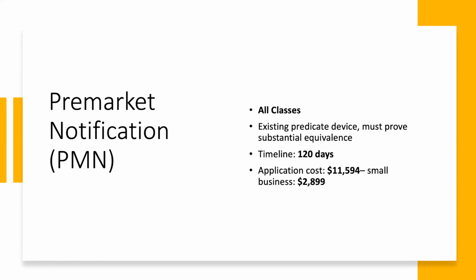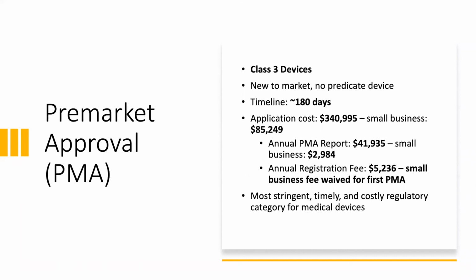If the FDA does review your application and says, you could not establish a substantial equivalence given the evidence that you have shown us to this predicate device, then they'll go ahead and shunt your application to a designated class 3 until it's reclassified as class 2, to either the pre-market approval or the de novo pathways. The pre-market approval pathway, as you can see here, the application costs are upwards of several $100,000 for a small business, closer to $100,000. And on top of that, you have to submit annual pre-market approval reports after approval, which is another several $1,000s. And with larger businesses, there's also an annual registration fee on top of that. So it's a very costly process, and the price increases every year by $1,000 to $2,000.